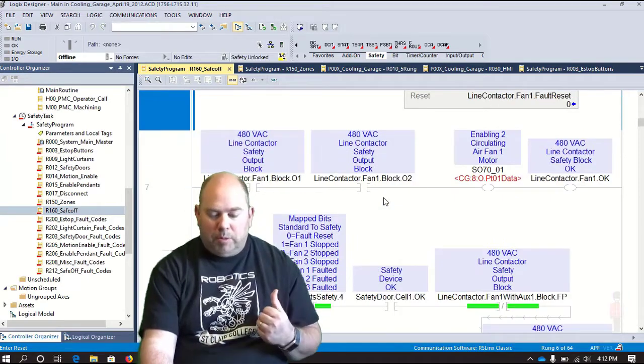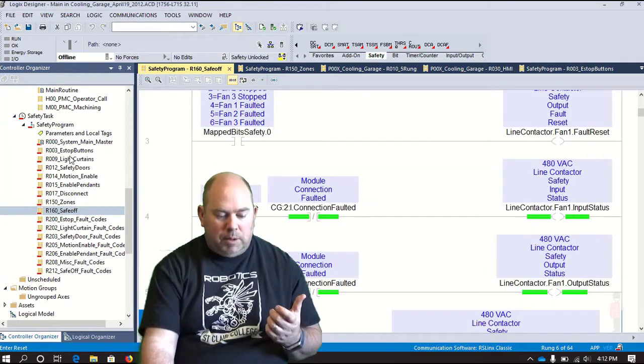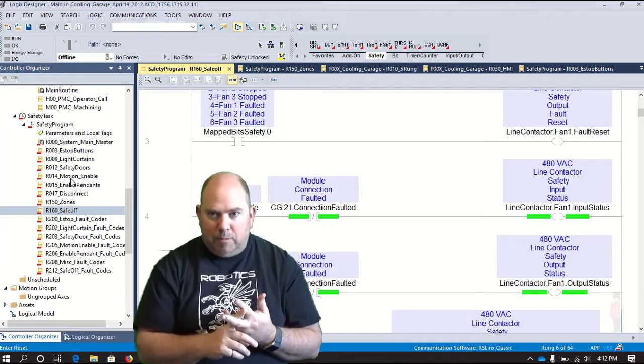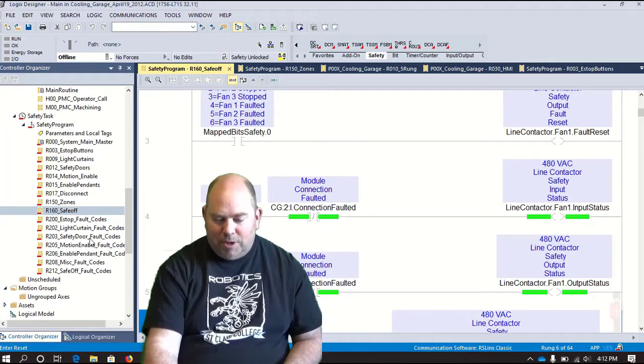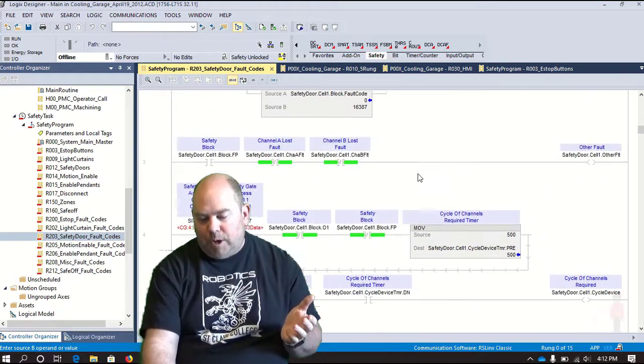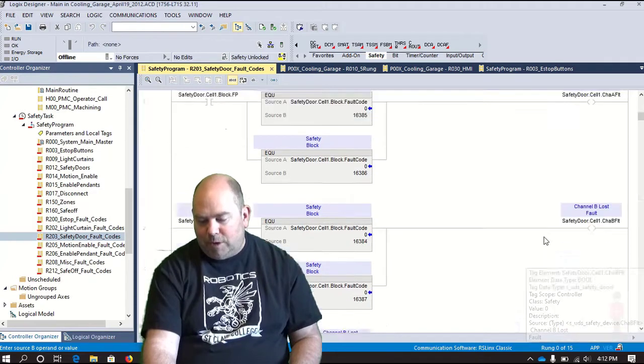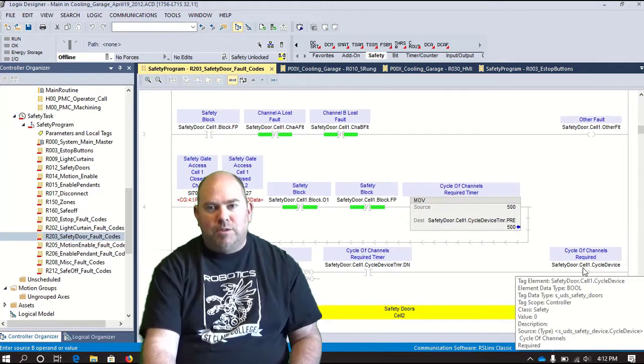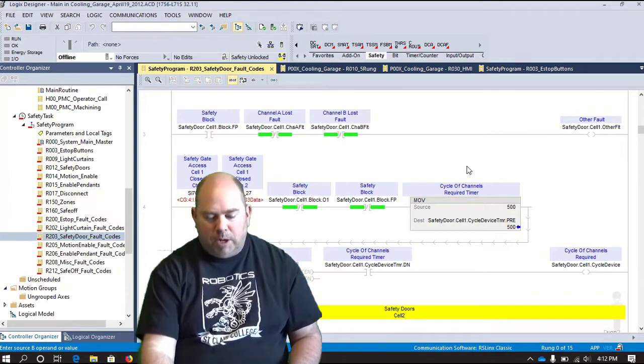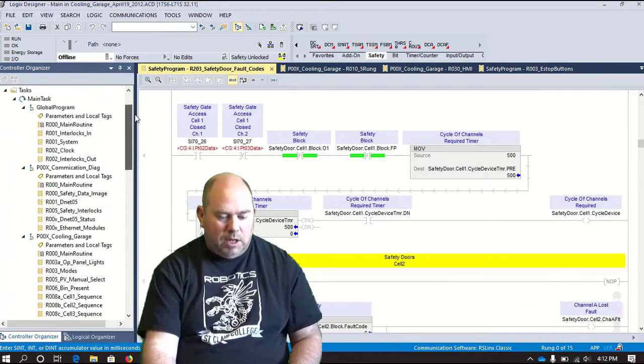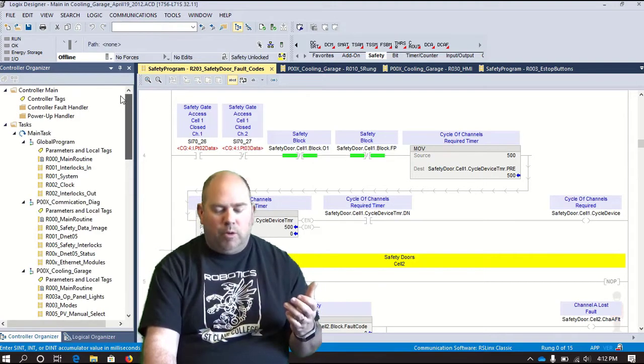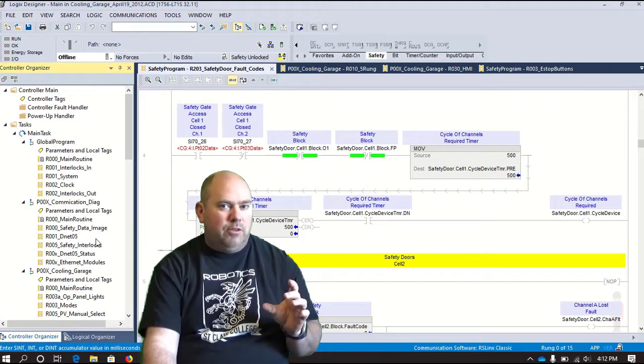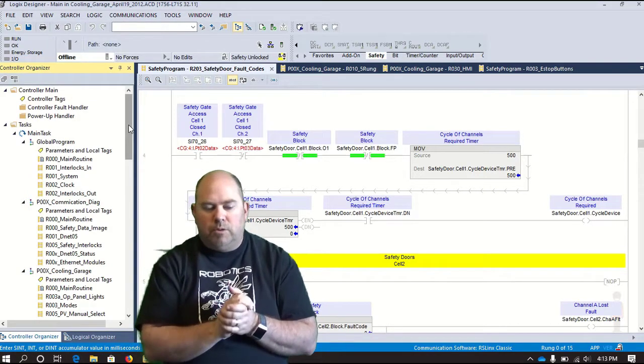So that kind of gives you an idea, basically, that is real-life, real program, using all these things. You can see the program does get pretty big, even with just a couple devices. A lot of this is trying to pull all the fault codes out of this. So about four lines are getting fault codes, basically getting a channel A fault, channel B fault, an other fault, and a cycle device fault. This would be, this actually requires you to cycle the device to make it work again. But that is a real program. You can kind of see how big of that, how much code is involved in this. But a lot of it is redundant code over and over again. And a lot of this is things that you would recognize very easily for coding. Okay? So that is a real safety program.